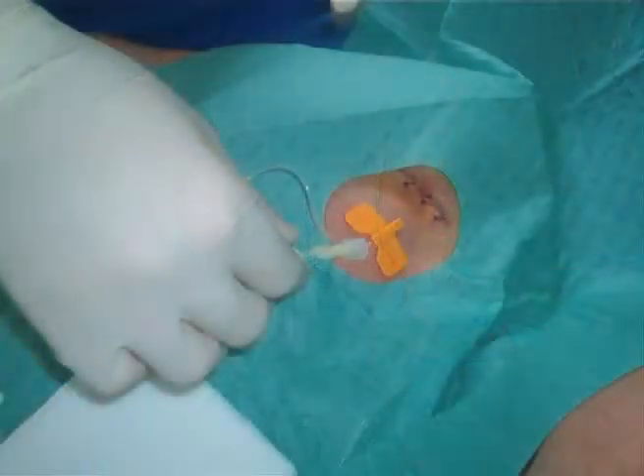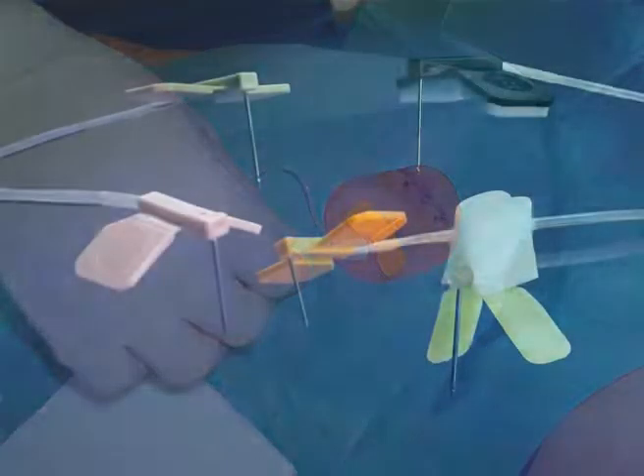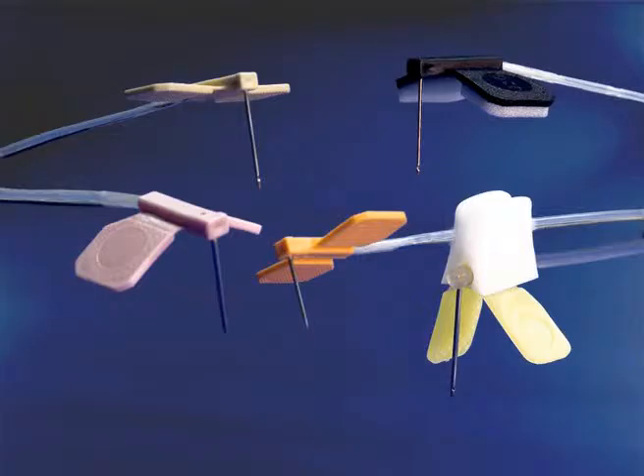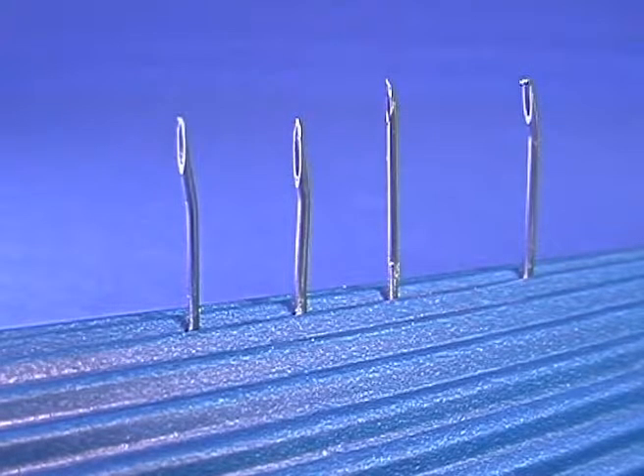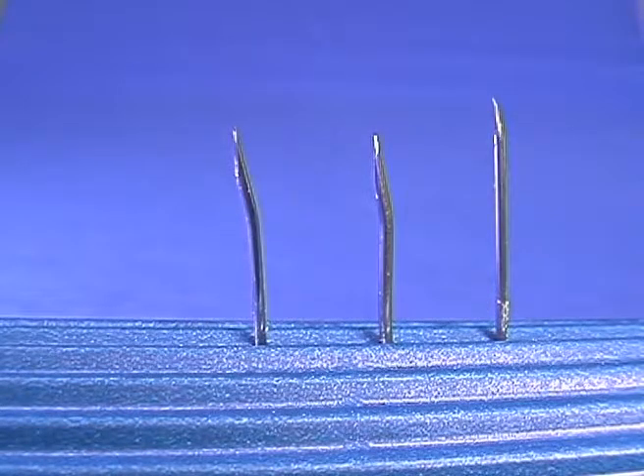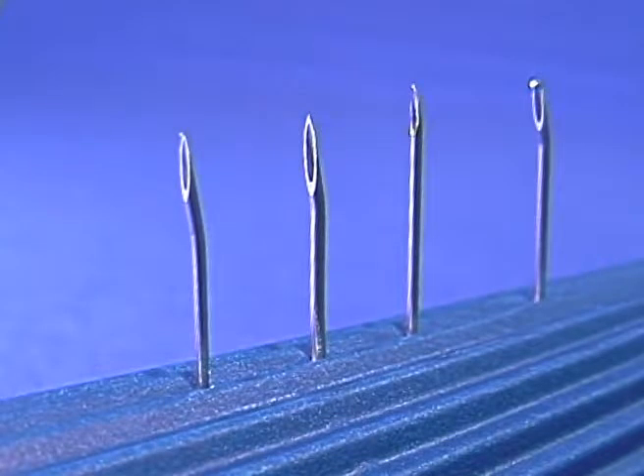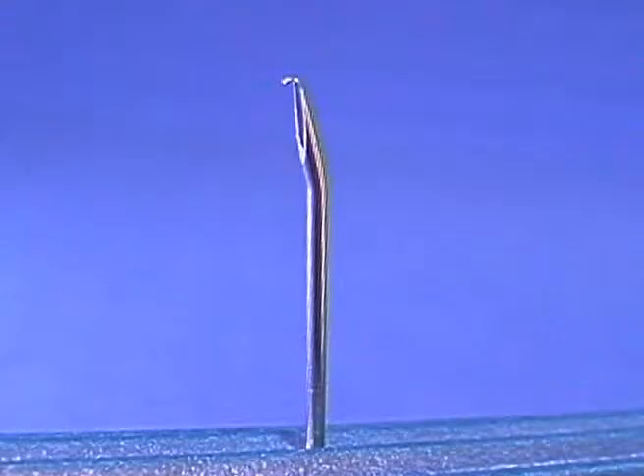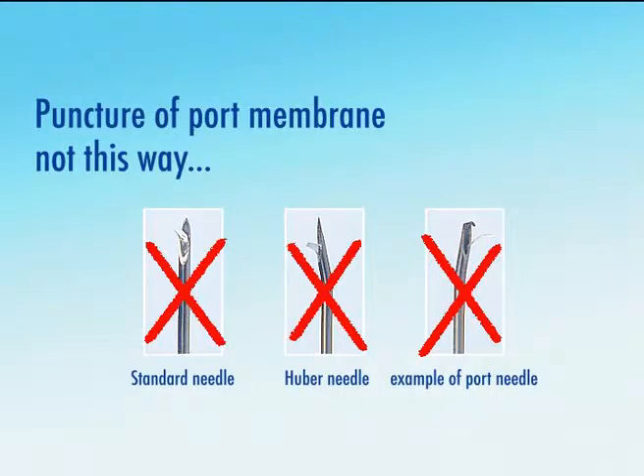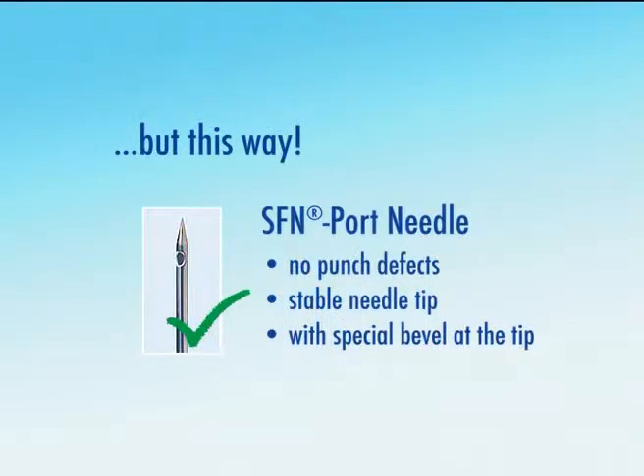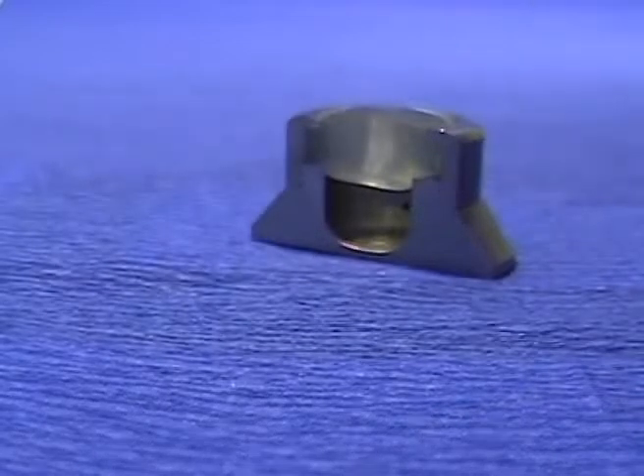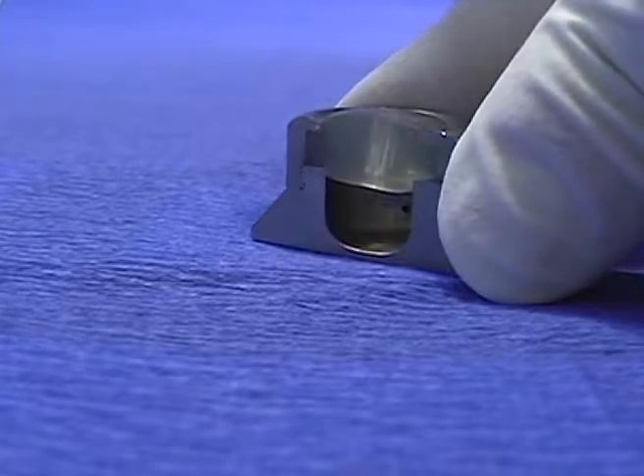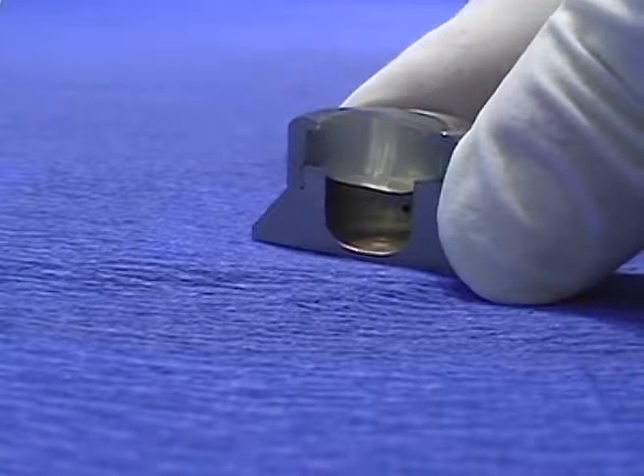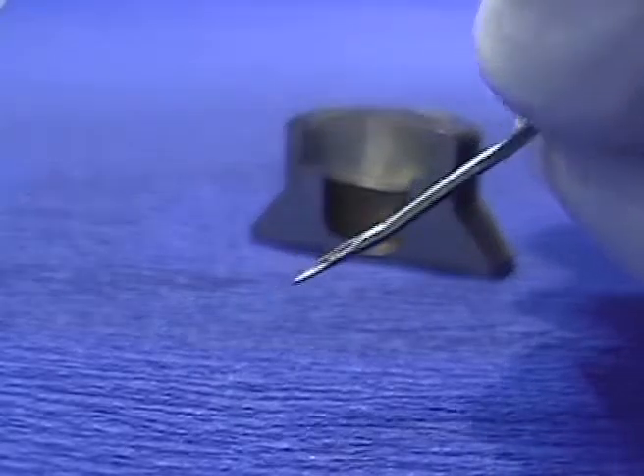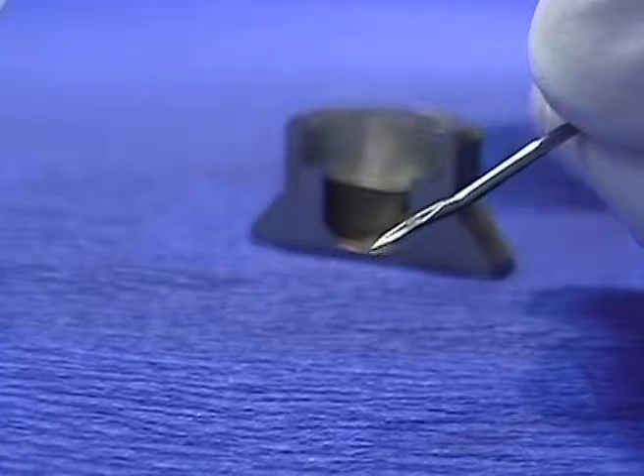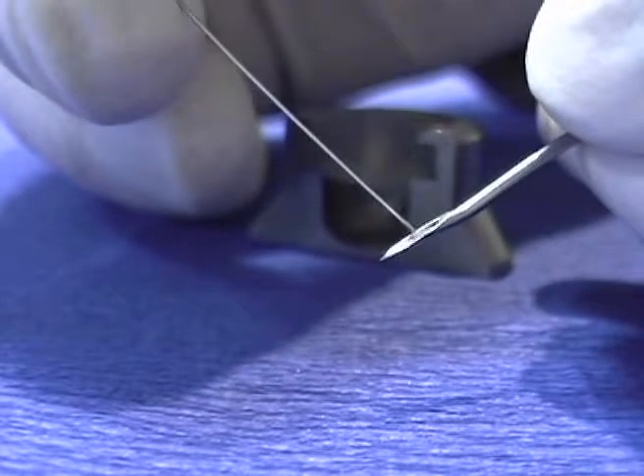The use of adequate port needles to avoid punch defects is essential in avoiding complications and increasing duration of implantations. Several so-called specialized needles with Huber bevel variations, presently available on the market, do not fulfill these requirements. They can cause punch defects resulting in liberation of silicone particles as well as needle bending. This is a demonstration of how a port needle can punch out tiny silicone particles which can enter the bloodstream. They may also cause occlusion or leakage of the port system as well as other complications. These microparticles are generally not visible to the naked eye and are sometimes lodged in the lumen of the needle. Recognition of this is often missed and the consequences underestimated, which may lead to complications.